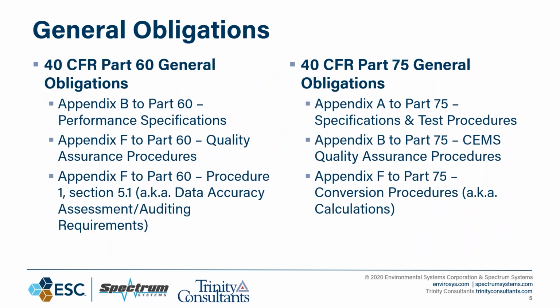When it comes to the subject of general obligations, most people fall under somewhere between Part 60 or Part 75, sometimes both. Under Part 60, your performance specifications occur in Appendix B, those specifications that you have to perform to. Appendix F under Part 60 gives you the quality assurance procedures, and Appendix F to Part 60, Procedure 1, Section 5.1, also known as your data accuracy assessment and auditing requirements.